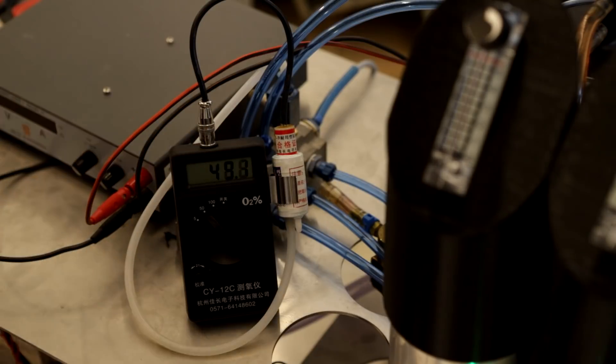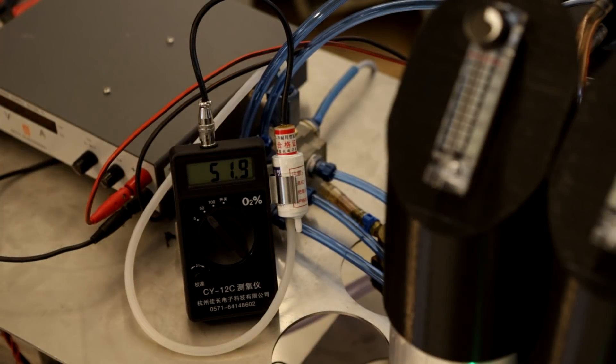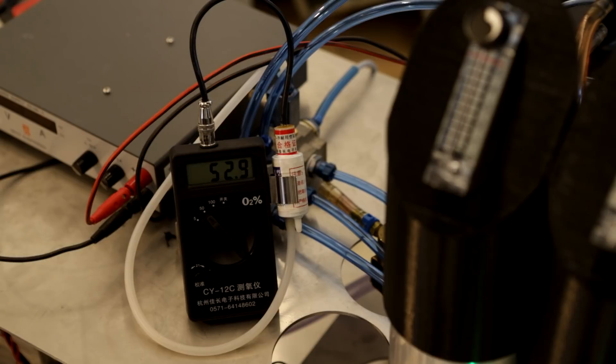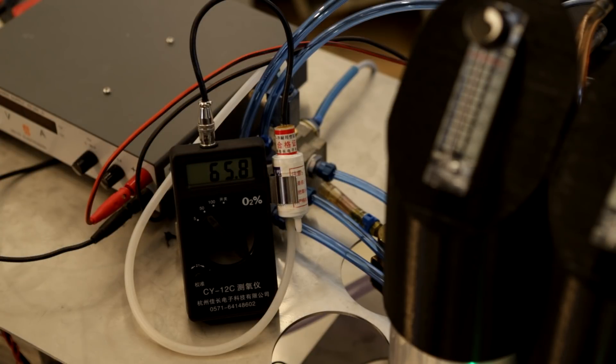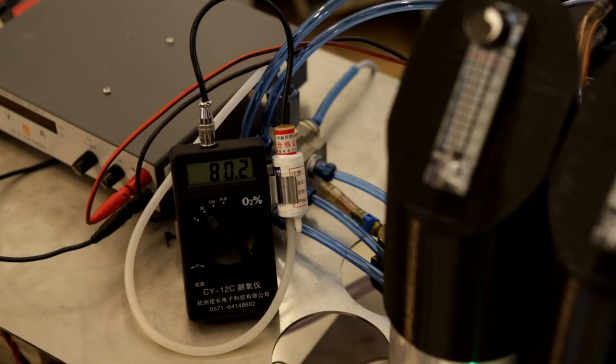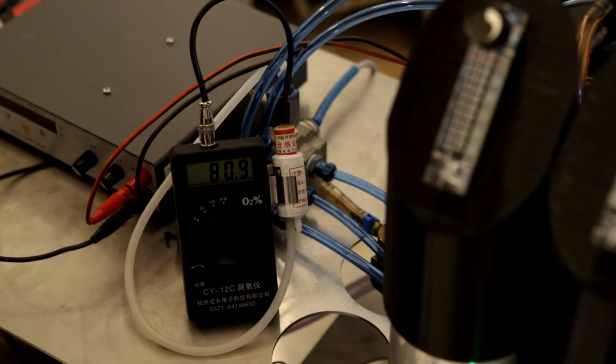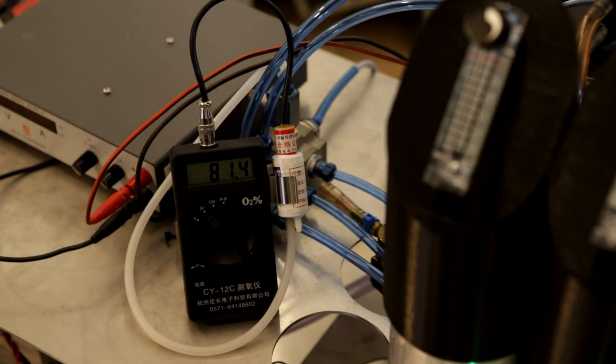Right, so it goes up pretty fast. This looks promising. 52. I set 5 liters per minute, which is the highest flow rate that we can have from the machine. So if it gets over 70 percent, then it's okay. 80 percent. 80 percent at 5 liters per minute. Wow, that's so good.